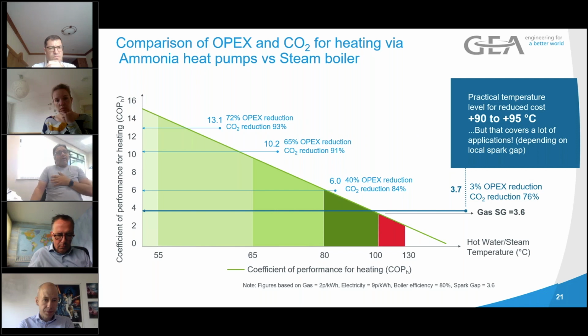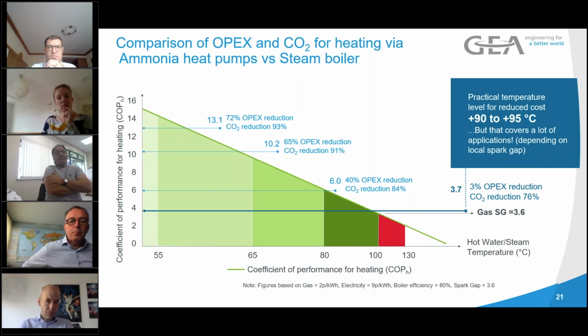So if you compare this with a boiler, we go back to our chugging boiler at 10 bar that's making steam at 160 degrees. Take the example of the juice where they melt the ice to produce +2 degree juice. They do that with steam at 160 degrees. I mean, that's madness. So what we do, we say, okay, we need heat, but as we go up in temperature, the efficiency goes down.